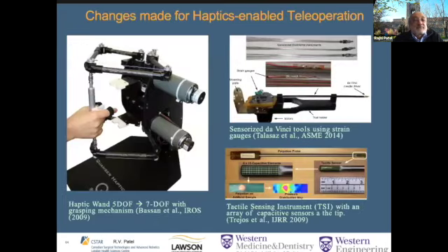Okay, just to show you the modifications that were done on the leader side, the haptic device was initially a 5 degrees of freedom device, and this was changed to 7 degrees of freedom with appropriate modifications. And one of the modifications was that we could also provide grasping force, which was not possible with the system that we purchased. And on the follower side, the instrument shown at the bottom here is the tactile sensing instrument, which had a 15x4 array of capacitive sensors. And the one above is the da Vinci instrument, which was sensorized. In this case, what's shown is the sensorization with strain gauges. But what we have done more recently is using fiber Bragg gratings.